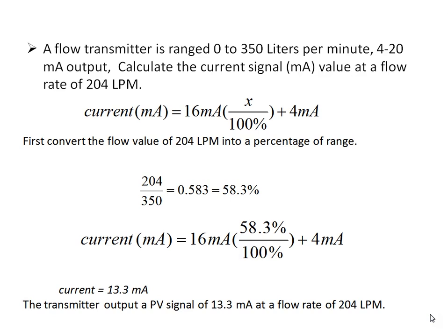Here, X is the manipulating variable. In this next example, a flow transmitter with a range of 0 to 350 liters per minute gives a 4 to 20 mA output. We need to calculate the output signal current when the flow meter reads 204 liters per minute. Using the equation: current = 16 mA × percentage variable + 4 mA. First, we convert 204 lpm into a percentage value, which gives approximately 58.3%. Substituting this into the equation, we get a current of approximately 13.3 mA.